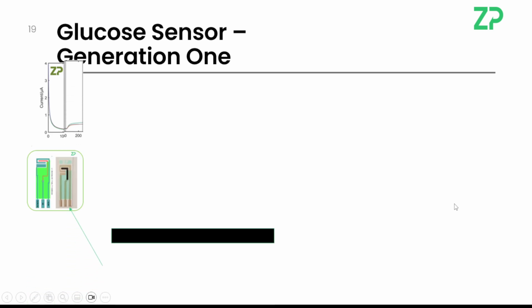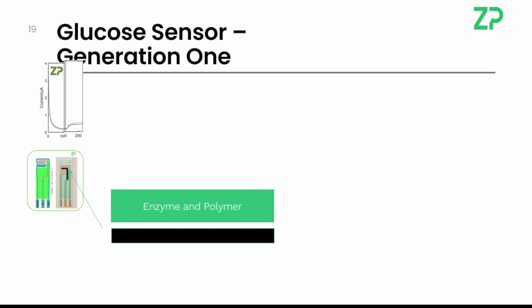Now, bringing this slightly closer to an actual glucose sensor. In a glucose sensor, you can end up with an electrode. You'll put an enzyme layer on it, and you'll put a barrier layer on it. On the previous slide where I had that membrane in place, I was really describing the barrier layer situation, but now I'm adding an extra layer, which is the enzyme layer.